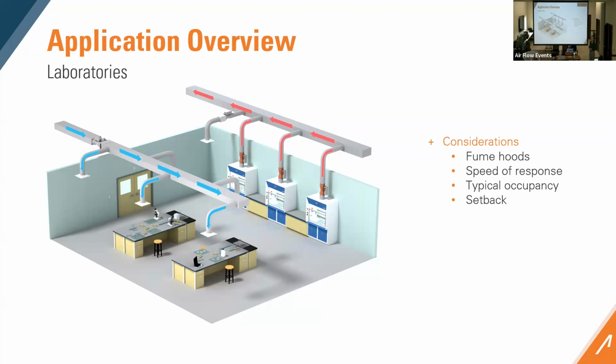But we have a new line of pressure monitors that we just released called Loom. There are 3 different levels. We have our basic pressure monitoring, which would be our Loom 10. That's single room pressure monitoring, and it doesn't have any BACnet connectivity. So if you're in a smaller facility that doesn't have a BAS system, that would be a good opportunity to apply that option.